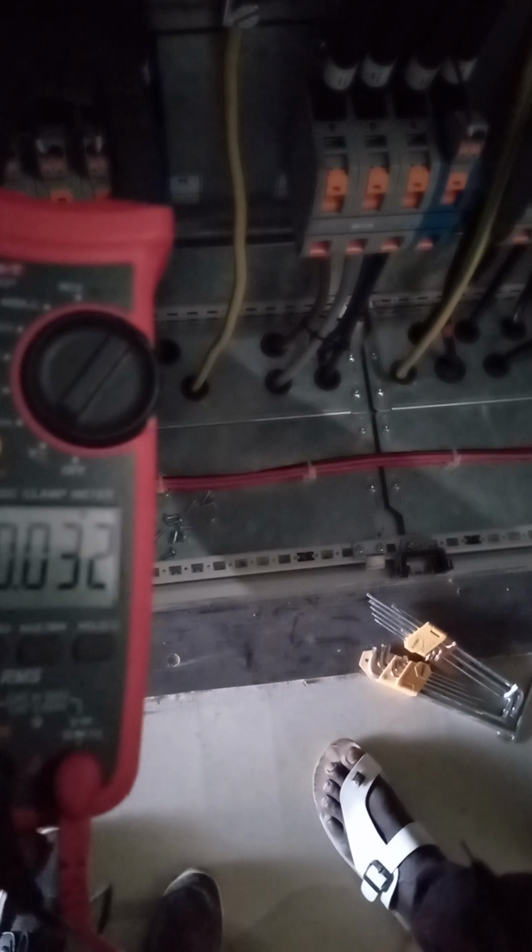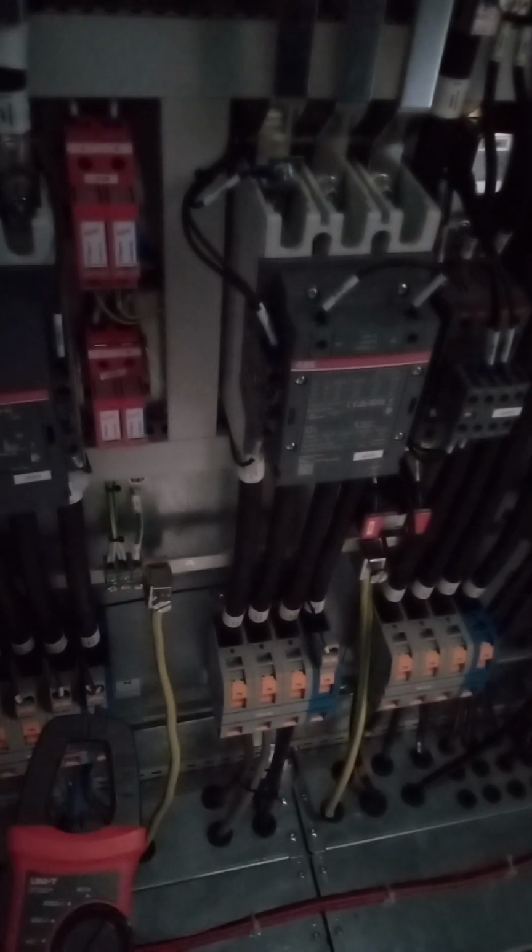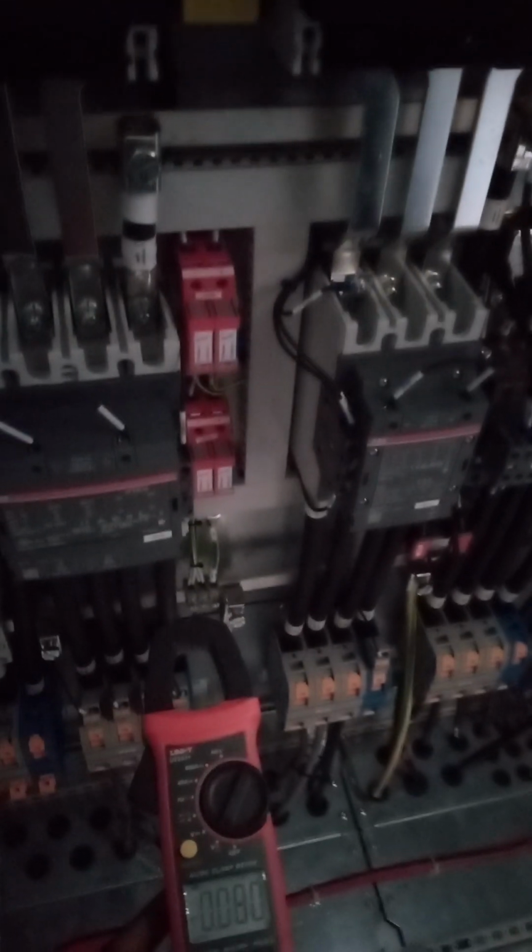Line 3 and ground, no power. Implying that the reason why we don't have power getting to the load is because we have this contactor that is faulty. It's energized, the coils have power, but it's not turning on. Thus, the solution is possibly a replacement of this contactor, and we see how things go in the near future.